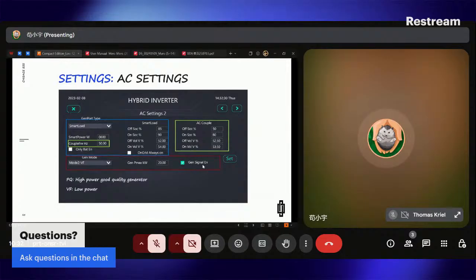This page is about the generator port. We can connect the smart load and on-grid inverter and the generator to here. When you are using a generator, if your generator is high power and good quality, their output is very stable, then the inverter will follow the voltage and the frequency of the generator. We can use mode 1 PQ to control it. If your generator is low power and the output is not so stable, then we need to select mode 2 VF and adjust the INV voltage rated and hertz rated on another page, so that you can still have stable output.